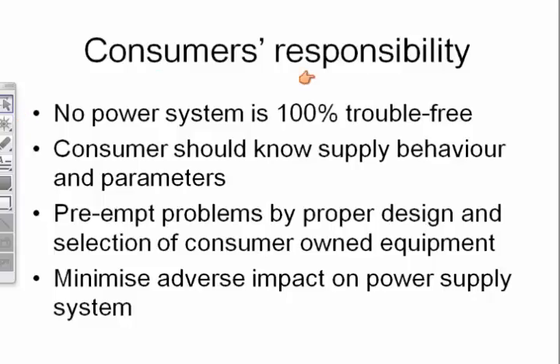The consumer's responsibility, remember, as a customer, you can't expect everything to be 100% from the utility. There will be occasional issues. So consumers should know supply behavior and parameters, and preempt problems by proper design and selection of consumer-owned equipment. For example, if you are running a factory, your equipment needs to be rated to run at slight under voltage and slight over voltage. You don't want equipment that can only run at 100% of voltage and malfunction for anything else, because there will be some variation to voltage. There might be small variation to frequency even.